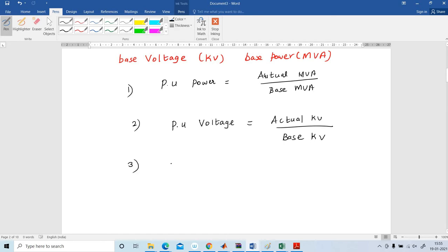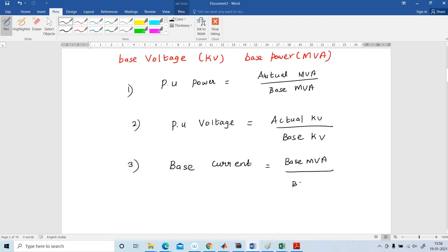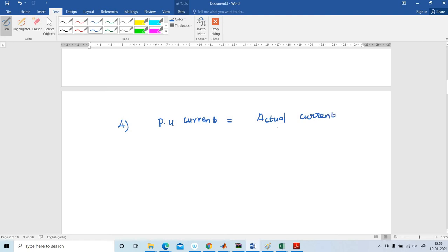Next, base current. From the per unit voltage equation we cannot directly find out per unit current. First we should know what the base current is. Base current is base MVA divided by base KV, and that is expressed in kilo ampere. Per unit current is equal to actual current divided by base current.